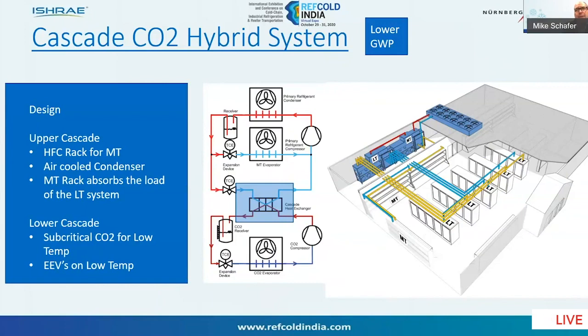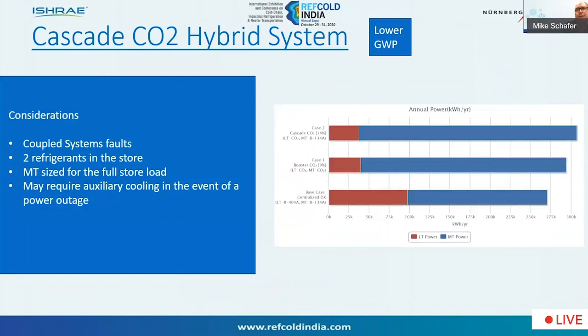So the medium temp system would more than likely be an HFC rack, would have an air-cooled condenser, and the other aspect of it is that the medium temp would be designed for the full load, including obviously the low temp heat rejection. So looking at the considerations, we've already talked a little bit about the power consumption. As with CO2 transcritical, these are closely coupled systems, so a fault on the medium temp side can affect obviously the performance, the uptime on the low temp. Medium temp is sized for the full store load, as I mentioned, and then given the high standstill pressures on the low temp, you may still require some auxiliary cooling in the event of a power outage.